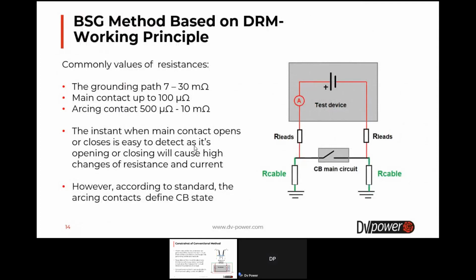So first I will try to explain the working principles of the test methods based on the dynamic resistance measurement. For that we have to know the common values of the resistances which are important for this measurement. Those are the grounding path resistance, which is in the range from 7 to 30 milliohms. Main contact resistance is up to 100 microohms commonly, while arcing contact resistance is from 500 microohms to 10 milliohms. So the instant when the main contact opens or closes is easy to detect, as its opening or closing will cause high changes of the resistance and the current. However, according to standards, the arcing contacts define circuit breaker states, and we will go through those definitions.